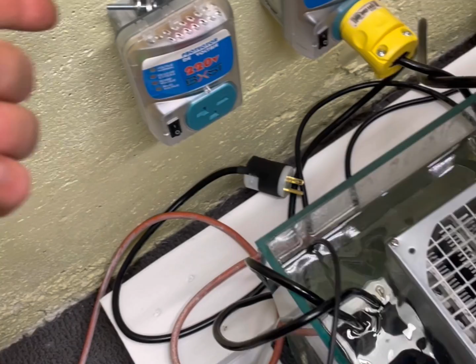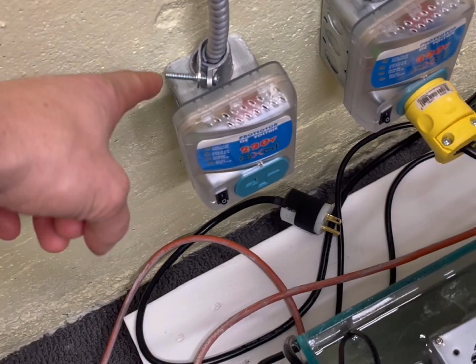For example, this is a 20 amp 240 volt double pole breaker, so if you multiply that you get 4800. This setup will be consuming about 3100, and the other setup about 3400. So at 3400 to 4700, I'd be within the 80% rule, just to make sure you're not going to get any overheating or make it unsafe.